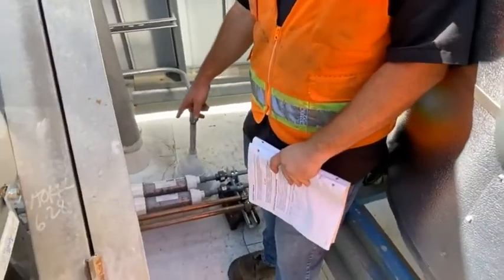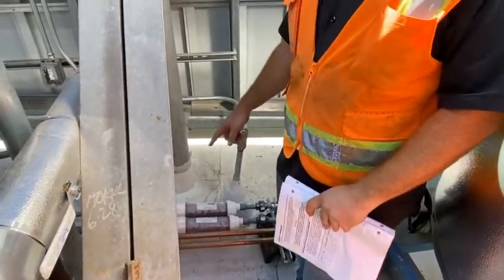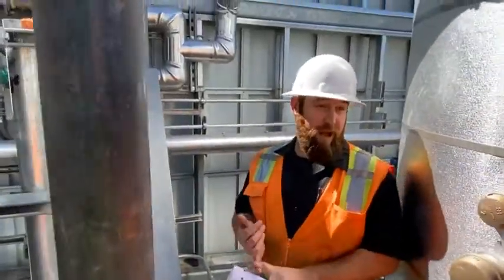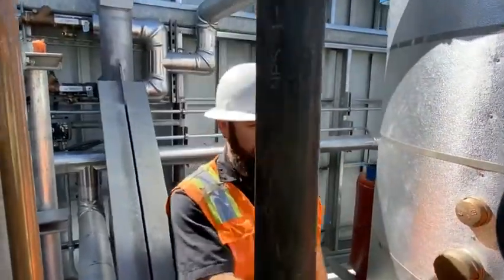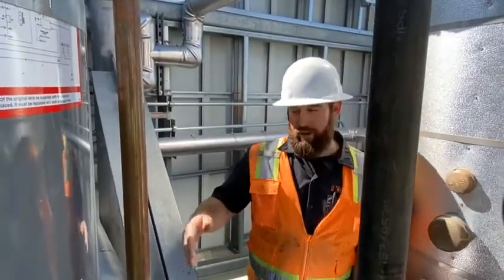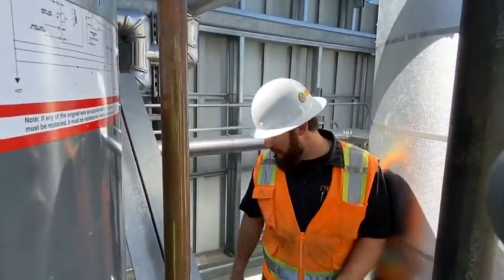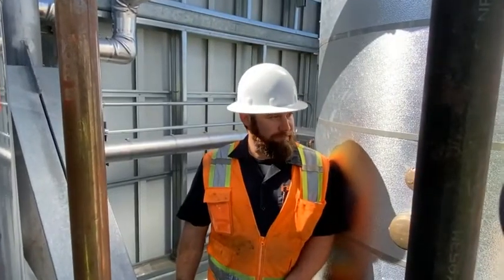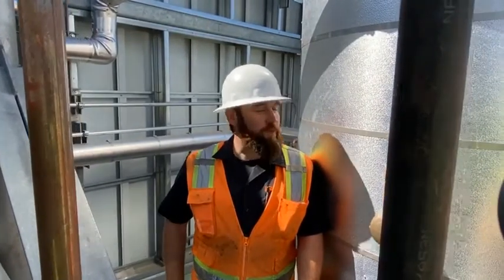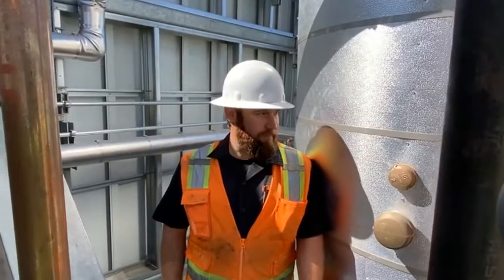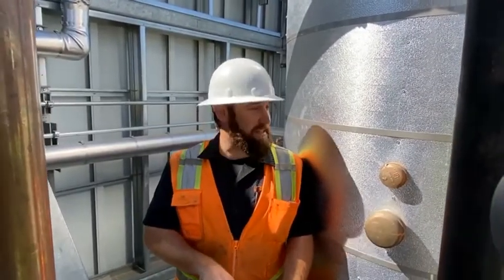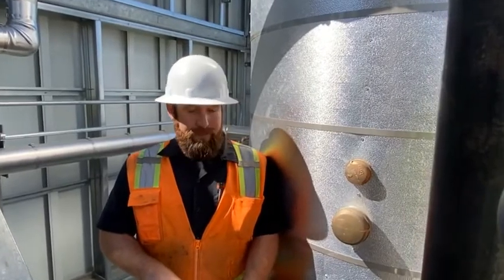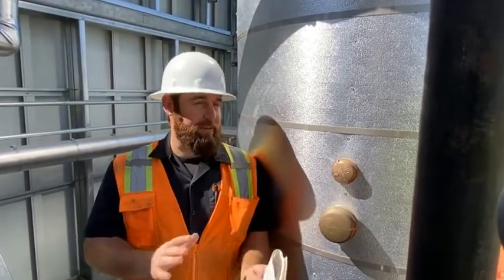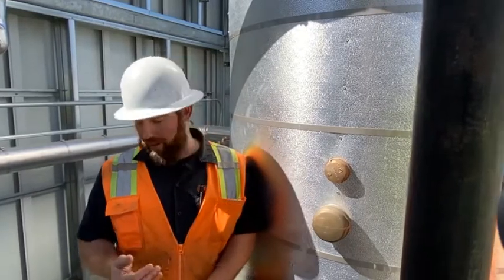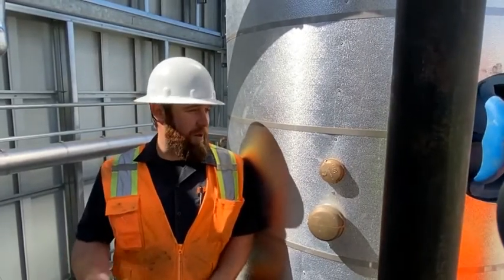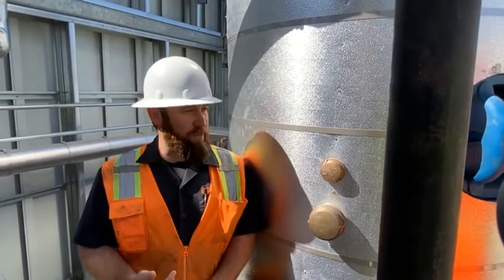So these are the neutralizer kits. You want to make sure if it's clogged, you don't see any water draining out here while the units are running. There will be a blocking issue on this if that happens. Also, those are for the acid, right? Right. So what's the maintenance on those? Here it says every 6 months to check it. I would say it's kind of a case by case situation. Check it. If it looks really black and dirty inside there, then you want to replace the pellets. I would say for sure replace the pellets every year.